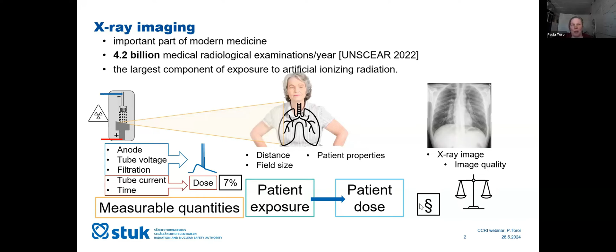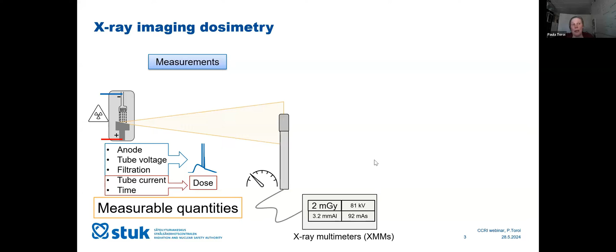And now, as we just heard from Sören's presentation, many hospitals are not using ionization chambers anymore in X-ray imaging dosimetry, but they're using semiconductor-based detectors, which provide not only air kerma, but also other exposure parameters. That's why we call them X-ray multimeters, XMMs. And you will probably hear this term many times today.